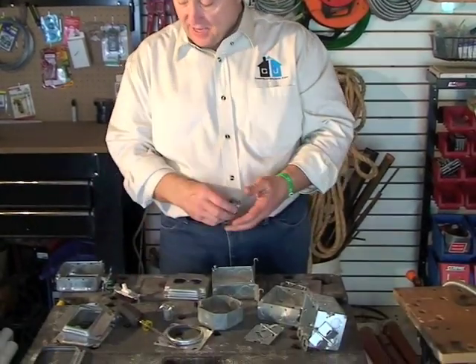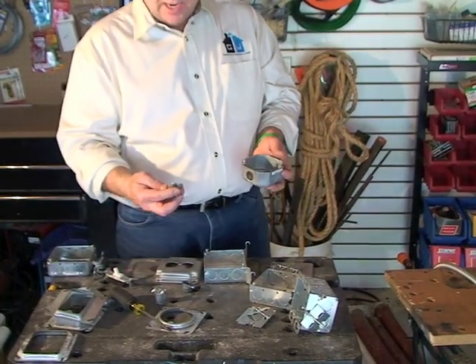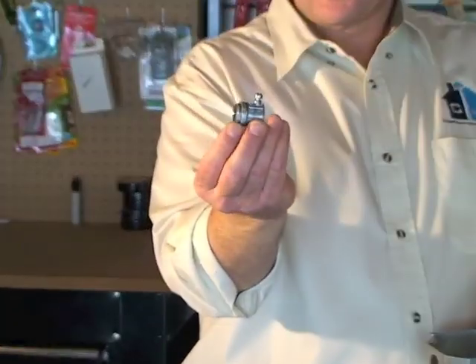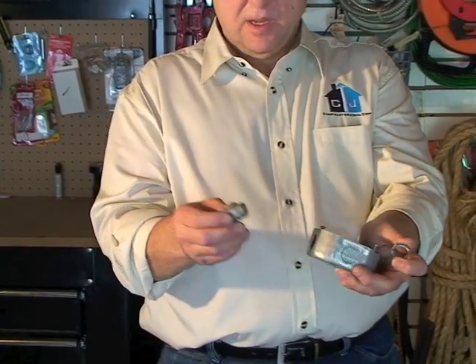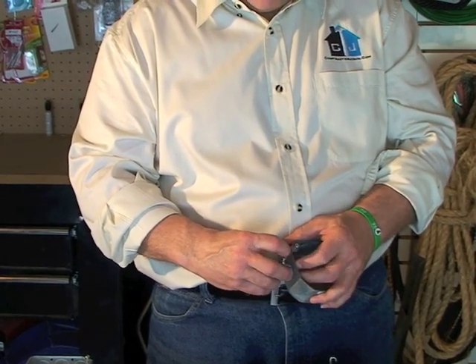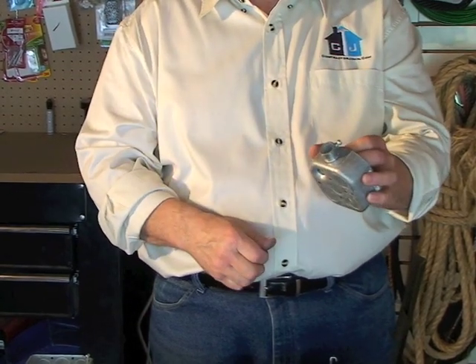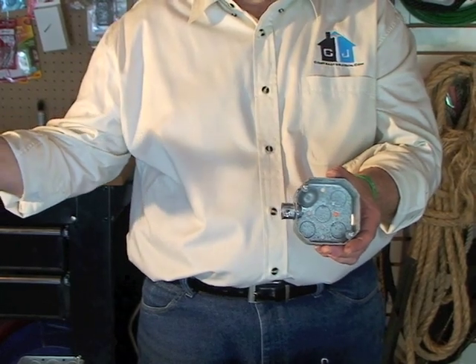Last we have our fittings. When you take any one of these boxes and you want to run metal conduit to it, this is a connector fitting. One part goes into the box and then the conduit fits right in here. Take this lock nut off, insert it in the box, take the lock nut on the inside and tighten it up, then take your channel locks and twist that tight. That allows you to run your conduit out.